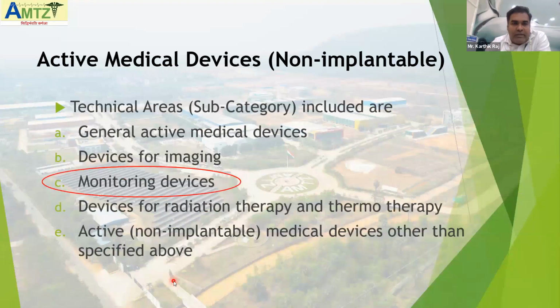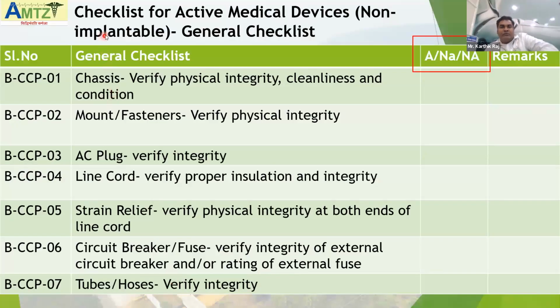Now first see the common or general checklist. This is the checklist for the active medical device, non-implantable. That is the general checklist. You can see that various points are written. The first point is chassis: verify physical integrity, cleanliness, and condition. That is the outer covering, the casing: is everything closed properly, is there any broken piece, and how the cleanliness is maintained. That part you are checking. In the next column, A stands for acceptable, NA with a small a stands for not acceptable, and capital NA means not applicable, and you can write remarks. In this way we are checking each point.